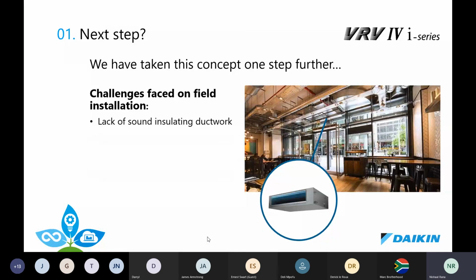So we've taken the concept one step further. This is done somewhere overseas. Most of you have seen the industrial looking shops, like coffee shops and so on. So you can also insulate the ductwork, and you can insulate the sound sensitive areas, and sound comfort is also key. The worst thing in a restaurant is having this buzzing noise from the indoor fan motor, because remember, the fan side or the air side of the circuit can still generate a lot of noise depending on what speeds you're running at. Because it's inverter, it will aim to always run at 50% or 40% speed, but it does go up to 100 or 120% speed in the case of a very warm day where the ambient air coming in is quite warm.